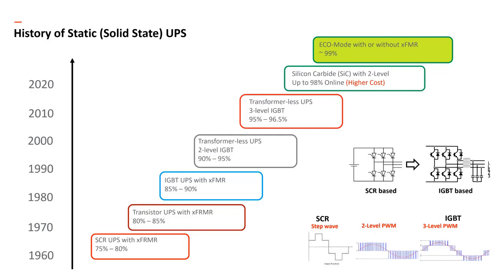From back in the 60s, where the UPS power modules were SCR-based thyristors, to bipolar transistors, and now lately IGBTs. So where most UPSs are today is the red box, the third from the top, transformerless UPS with three-level IGBT power modules. There's a next generation semiconductor around the corner. There's actually one UPS out based on this topology that can drive the efficiency a little higher.